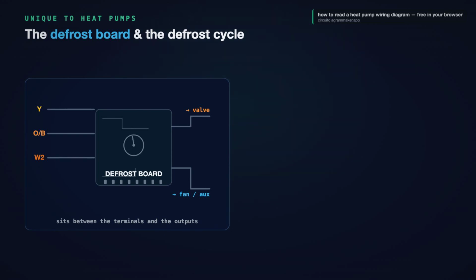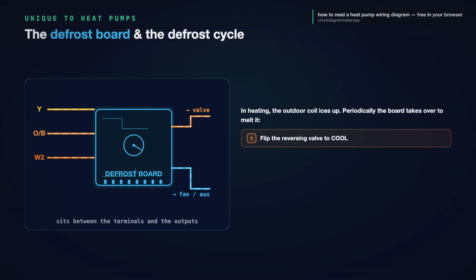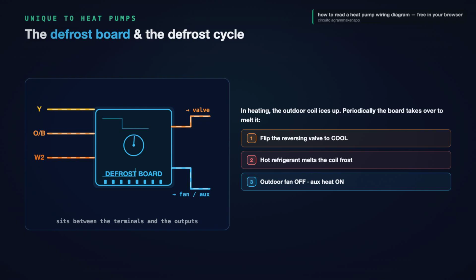Now, the part that is truly unique to heat pumps, the defrost board. In heating mode, the outdoor coil runs cold, and frost builds up on it. To melt that ice, the defrost board takes over. Periodically, it flips the reversing valve back to cooling for a few minutes, so hot refrigerant flows out to the coil and melts the frost.